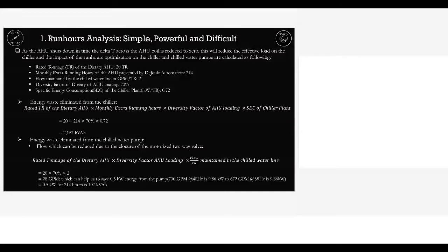And what is the diversity factor for AHU loading? That means in a room, the occupancy does not remain constant. It changes with time. Sometimes it is peak occupancy in the morning and sometimes it is very low occupancy in the evening. That is where a factor comes. We call it diversity factor. And specific energy consumption, a very seasoned term. All of you might have heard it multiple times. In a chiller plant, we call it IKW per TR. So IKW per TR for the entire chiller plant, that is kilowatt consumption per TR of refrigeration, is 0.72. So this is the basic information you need to know while you step into the calculation to understand the impact of saving energy, by shutting this equipment down on time from the plant as well as from the AHU.